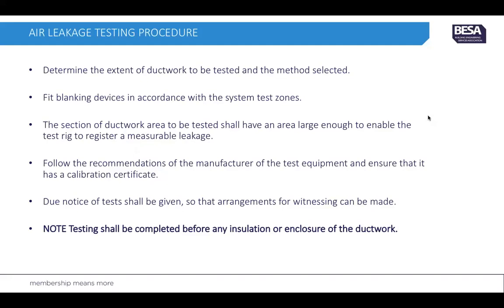Ensure that the test equipment has a valid calibration certificate. Due notice of tests shall be given so that arrangements for witnessing can be made. Testing must be completed before any insulation or enclosure of the ductwork; otherwise you cannot get back to rectify any fault.